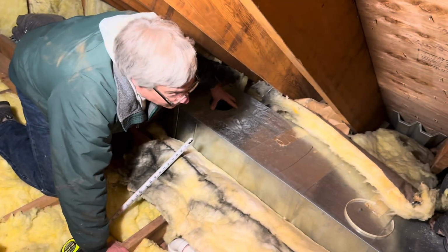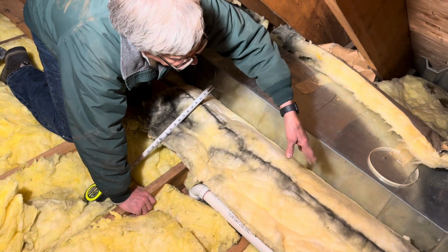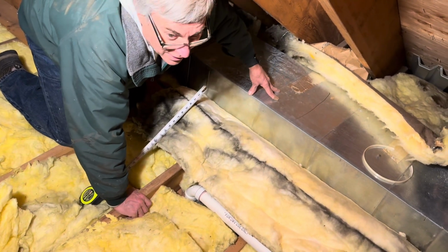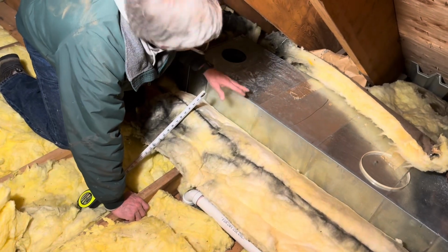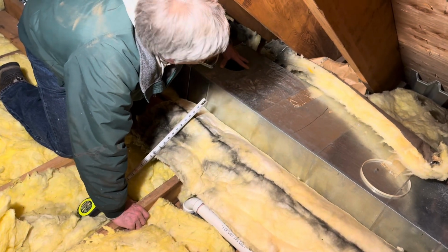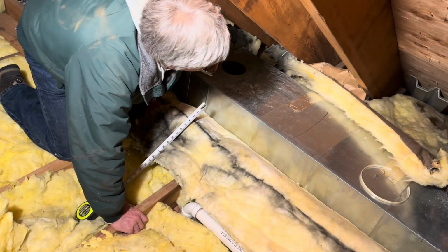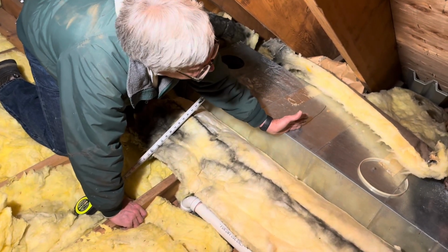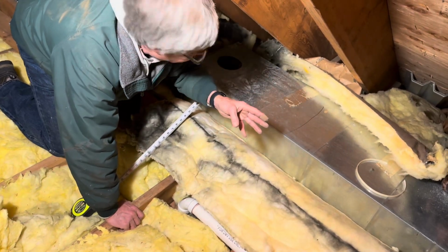So all of the pressure that should be pushing backwards to make sure that this duct is properly pressurized for each branch circuit that comes off is not. It means that this one is going to receive a lot of pressure and it gets to the end, and then it's not going to give enough back pressure here to equally pressurize those ducts. So the performance is going to suffer.